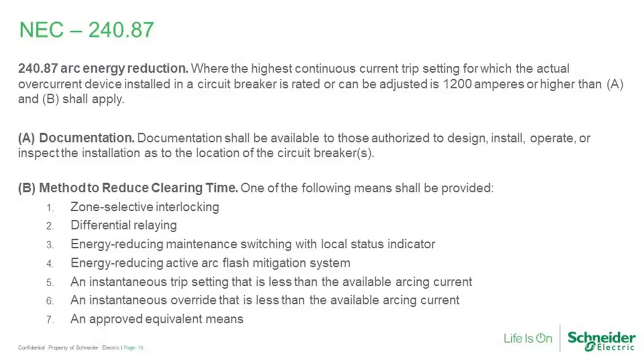But it basically says if a breaker is rated or can be adjusted to 1,200 amps or higher, you have to apply some method to reduce clearing time: either zone selective interlocking, differential relaying, a maintenance switch, an energy-reducing maintenance switch with a local status indicator, an energy-reducing active arc flash mitigation system, an instantaneous trip or instantaneous override that's set less than the available arcing current, or an approved equivalent means. So certainly lots of options there. But the point being, for these larger circuits where maybe more energy is available, we are now required by the code to put in some means to help reduce the energy levels.